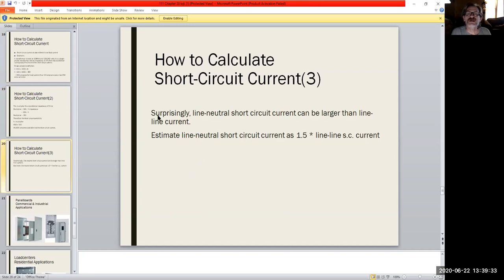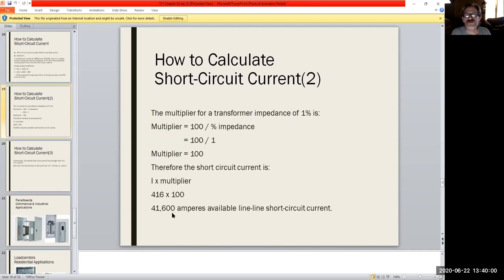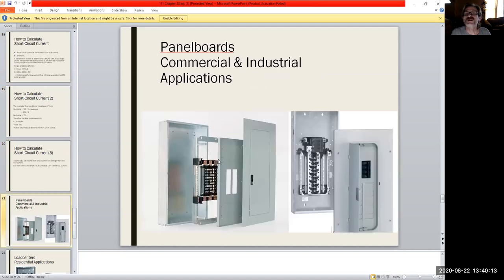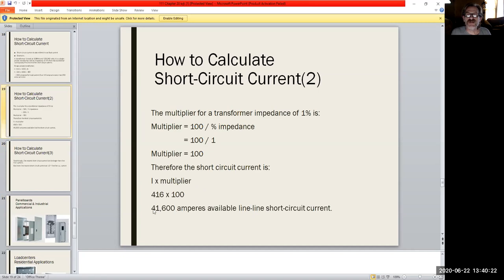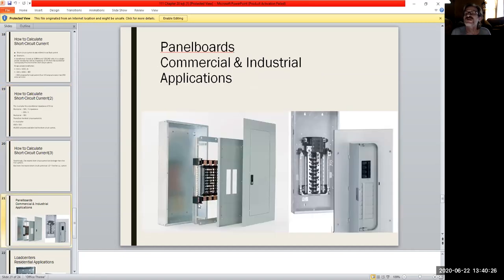And so how do you calculate short circuit current? Surprisingly, your line to neutral short circuit current can be larger than the line to line current. You'd have to look at how the transformer is involved and what happens when you throw neutral in there. But when you do that, believe it or not, this goes up quite a bit, to the point where it's like 1.5 times larger than your line to line. So if we were to go through that, it's 41,600 times 1.5. That's adding another 20,000 or so, which would make this quite a bit larger as far as what we would have to be rated for. So your equipment would have to be rated for this, so that it doesn't blow up when this kind of short circuit current occurs. But usually when that happens, it feeds back to your transformer and you hear that really loud explosion in the back.